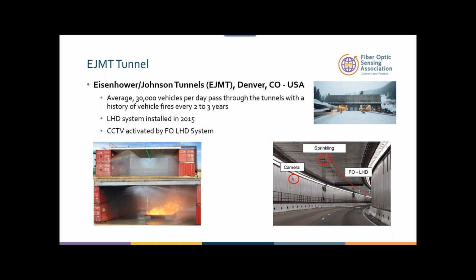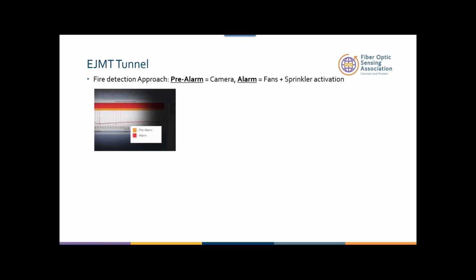In this case, it's very, very important. On the left, you can see a picture where they did a mock-up of this tunnel to prove that the fiber optic linear detection is the best system before doing the installation, which is on the right. The installation on the right means you have cameras, sprinklers, and the fiber linear detection as the red line on the right. The fire detection approach is very simple.